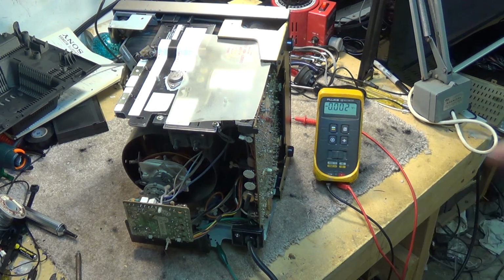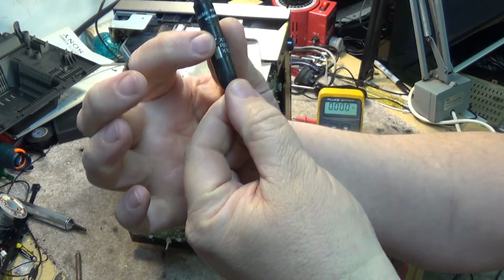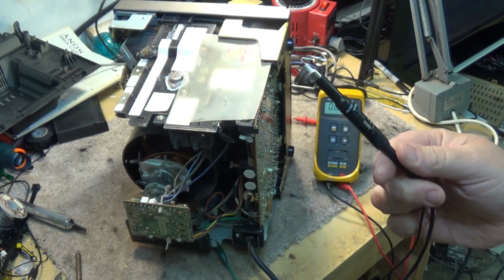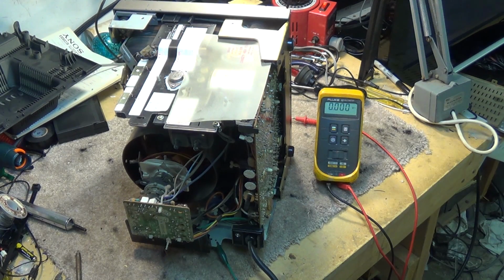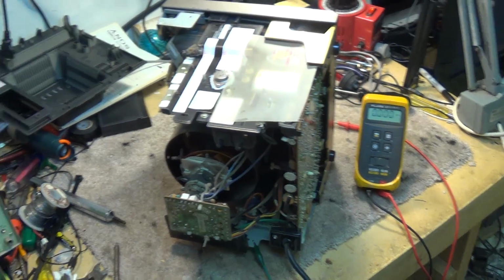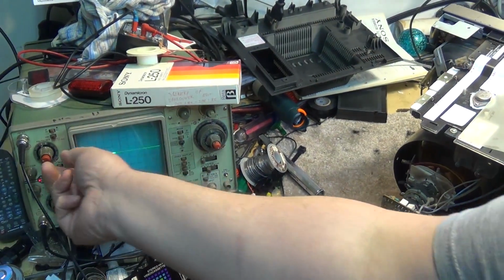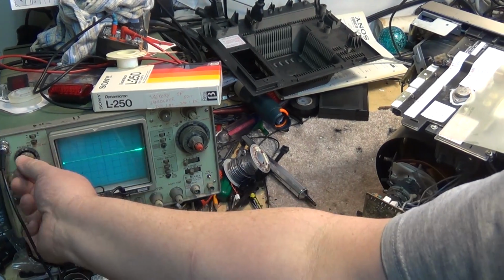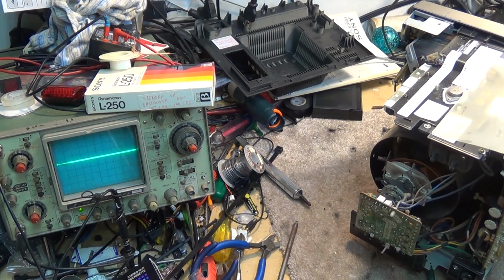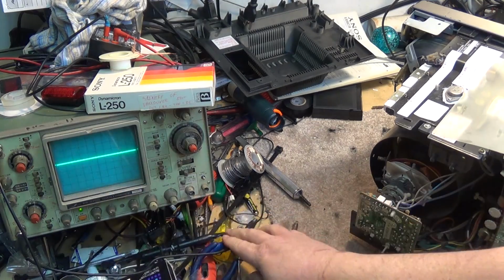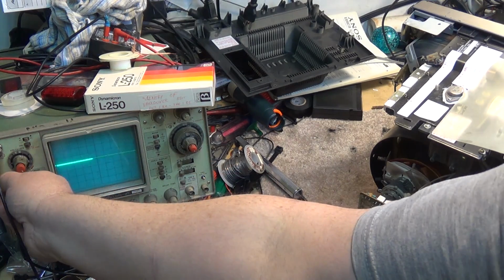So instead I'll use my scope with my ×10 probe. I select the ×10 input so I can measure a much higher voltage than the scope could normally handle -- the scope is good for about 600 volts, so with ×10 I can go well over 1,000 volts. I'll turn down the divisions to 10 volts per division, which becomes 100 volts per division with the ×10 probe, set it up for channel 1, and center it.